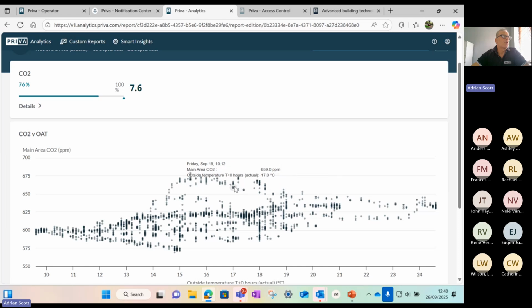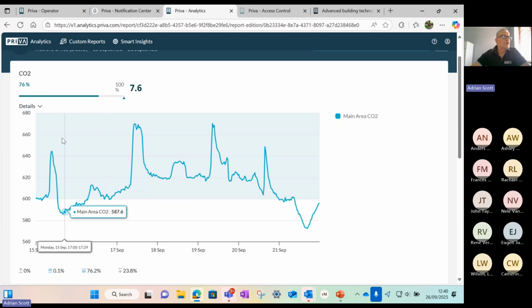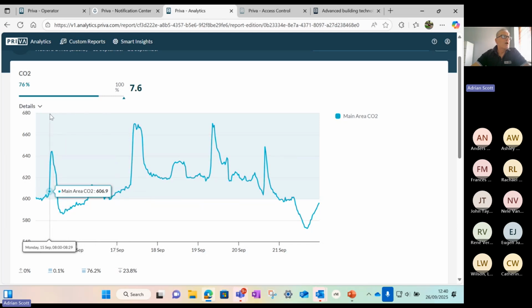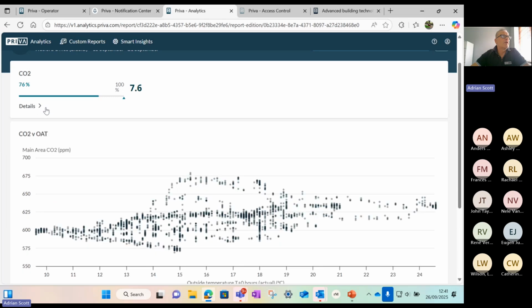But what we're able to do is create something called a KPI analysis. So you see here, 7.6 - what this is actually looking at is the ratio of times that we're between 600 and 680 ppm. This is showing me that I'm below limits 23.8% of the time. If we were above or outside, the controls are asking to achieve a set point, they're given an output, but what this is showing is that the mechanical plant would not be achieving that - there's an issue with the mechanical plant. So what we're using is the BMS to identify failures, or issues, or degradation within the mechanical plant that we have.